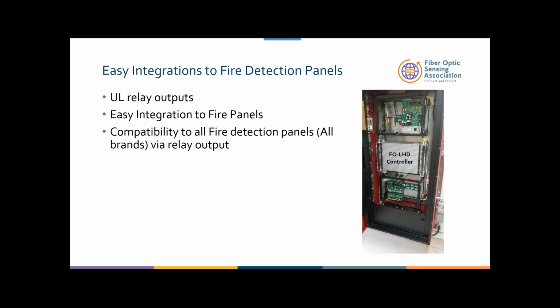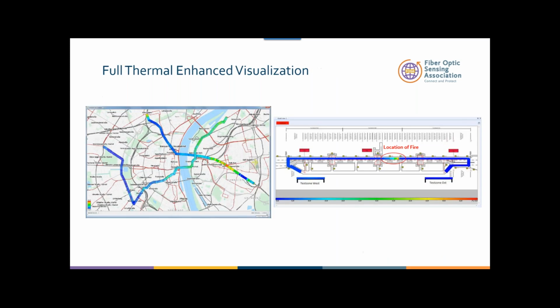The next advantage is the ability to be integrated to a fire panel. Most of the time, we are in the DTS world, distributed temperature sensing, but most of the time you hear people say Honeywell, Siemens or Tyco. There are so many different systems. The ability to be UL rated and to have UL relay outputs means integration to any fire panel system. The compatibility is just amazing.